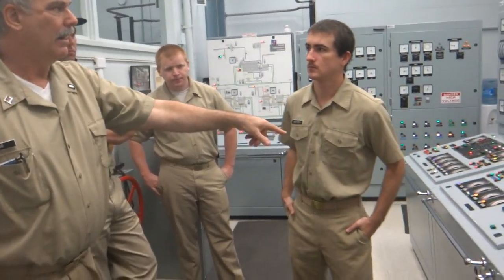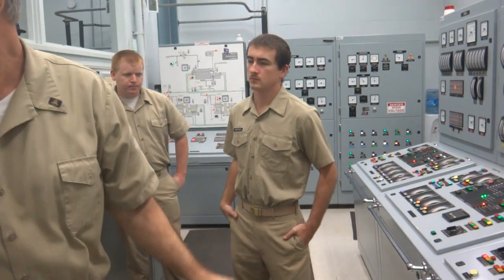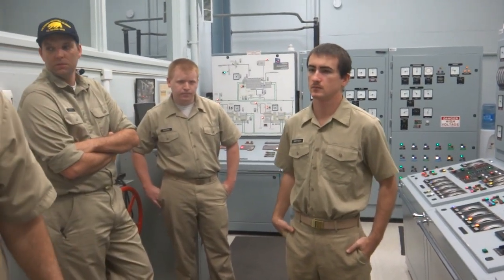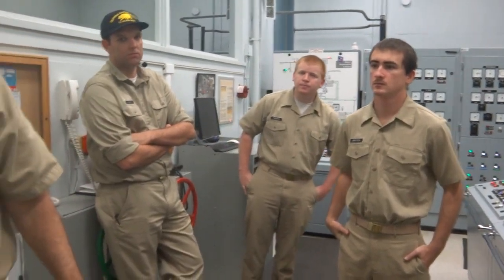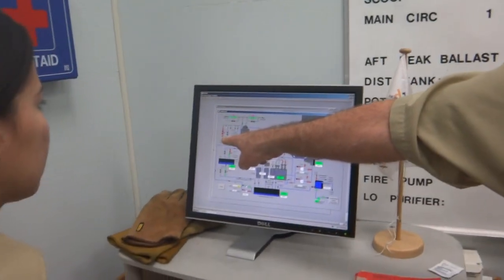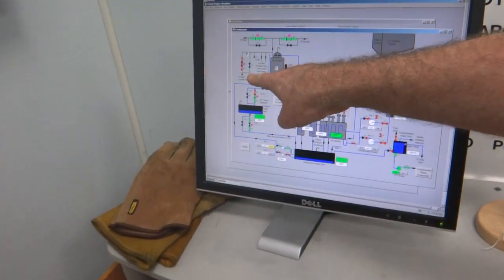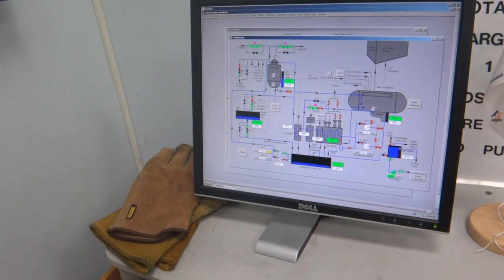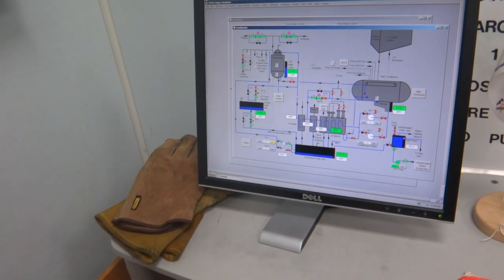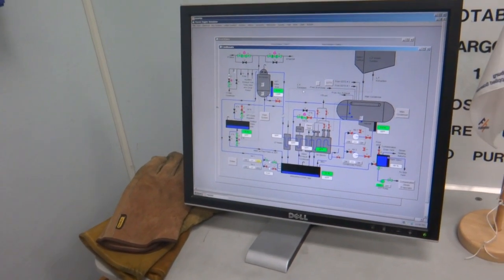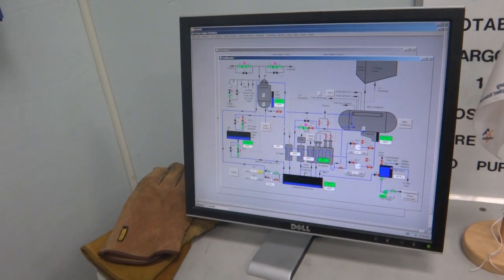Okay. Is that? Yes, you can do that. That's the dump. Yeah. With the spill valve, he'll get it up there. You have no control. This one you can get. This is for the auxiliary exhaust pressure being too high. That dumps to the condenser. Open that up. We're good there. Makeup feeds in auto. We're happy. All right, so what else can we do?